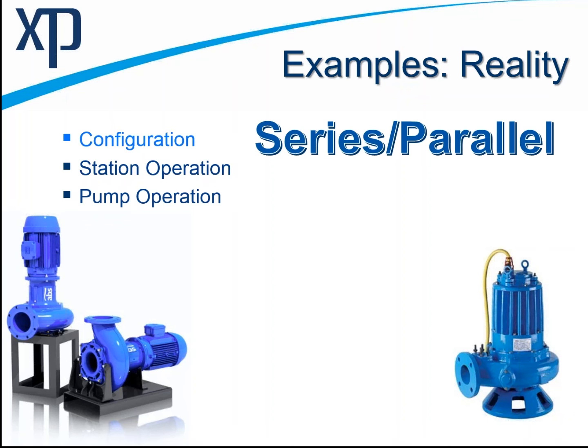You'll see that a lot in maybe groundwater systems. If you have a water distribution system that's fed on groundwater, you might have a really low flow, high head pump to get it out of the ground, and then that pumps into a different pump. But in the sanitary world, it's almost always in parallel. That has implications you'll see here in how the pumps operate.